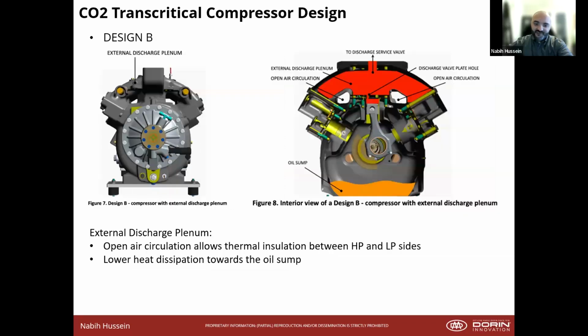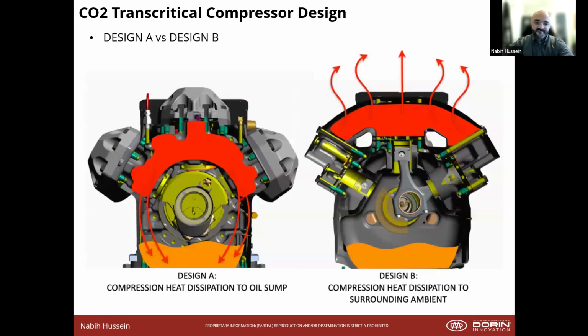And we have our external discharge plenum. Same thing, same compressor functionality. You're taking the internal and moving it externally, leading to a thermal cut between the high pressure and the low pressure sides, and lower heat dissipation towards the oil sump. This is how we're dealing with that first challenge of lubrication. And then here they are side by side. The theory behind it is to dissipate the heat exterior instead of interior.